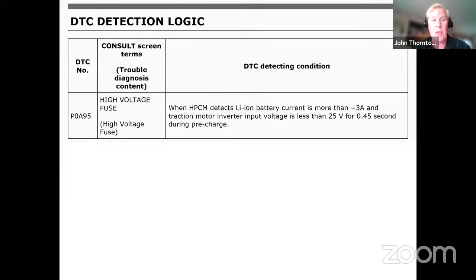I've made some modifications here, but the first one they list is harness and connectors, and please notice what they say in parentheses: high voltage direct current is open or shorted. Well, if you have an open, obviously there's no current flow, and depending where the open is, there may be no voltage available to the inverter. If you have a short, generally shorts blow fuses, and if fuses blow, we have an open anyway. So getting back to the code, it's a high voltage fuse code. Okay, maybe that makes sense.